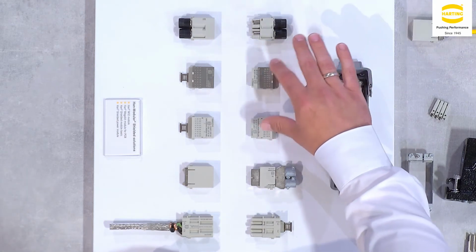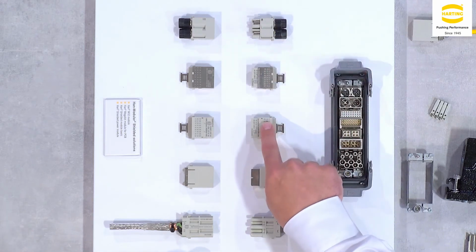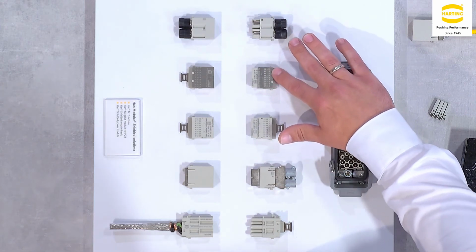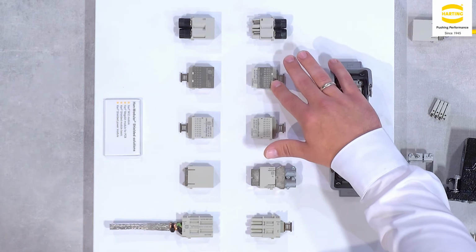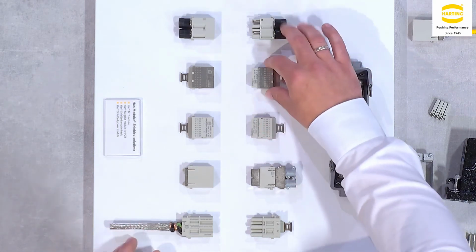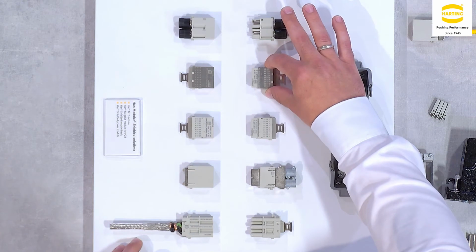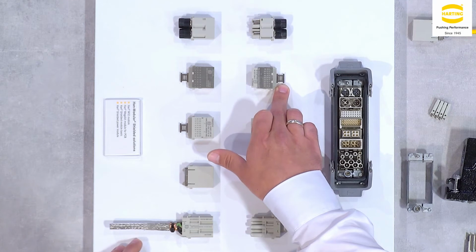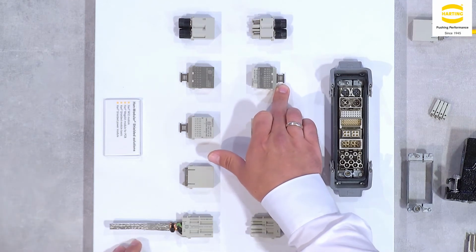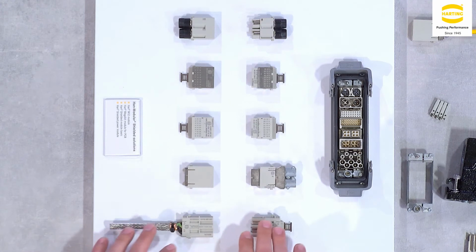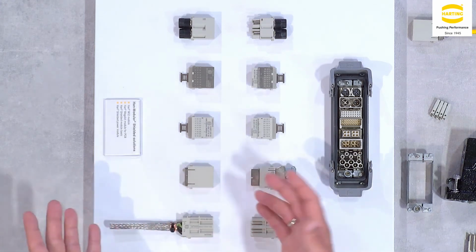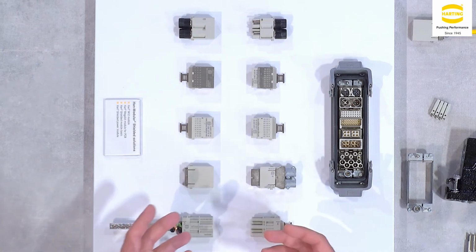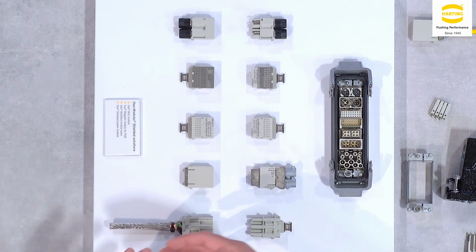So we have our shielded basic and shielded basic light module. The difference here, I hope you can see this in the camera, is that the shielded basic module has a 360-degree shielding, meaning that we have a metal cage around the isolation body, and the shielding can be attached right here at this little element at the end with an according zip tie. The zip tie will also be delivered by us because it's a special zip tie that can withstand the temperatures that are qualified within our connectors.